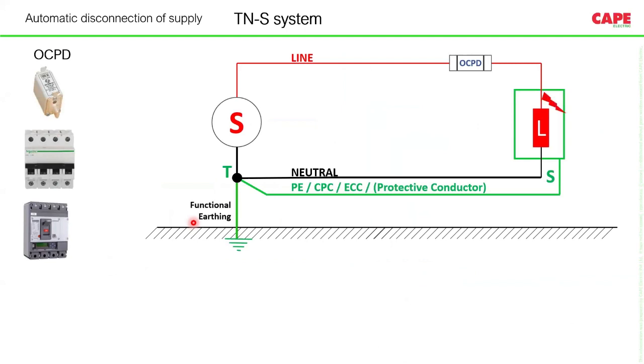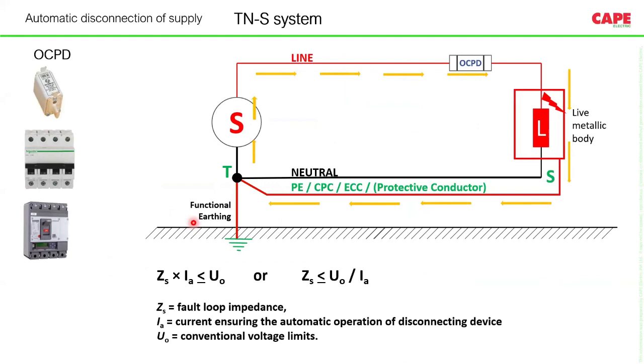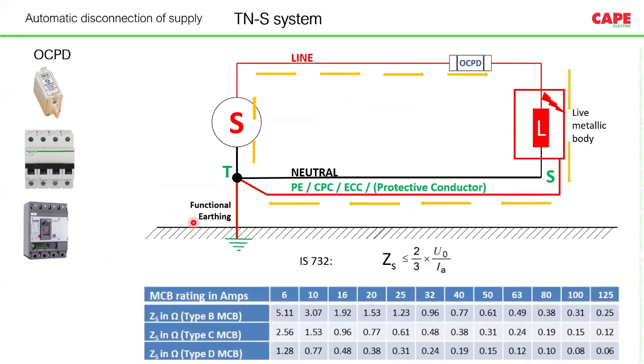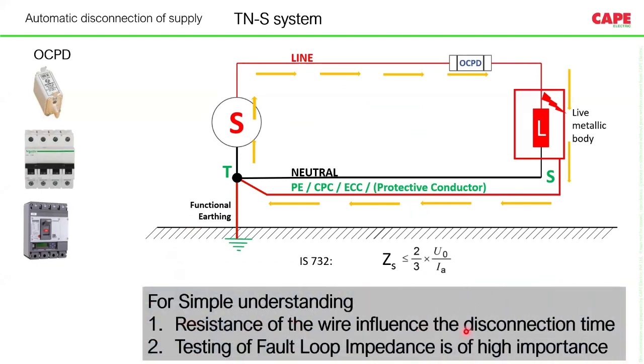Another important subject is fault loop impedance. Engineers who are practicing in hospitals, please note that equipotential bonding and fault loop impedance are both highly important. Both are included with very good explanations in the National Electrical Code. You can also find the tables, with fault loop impedance recommended for each type of MCB. So the simple method which you should understand is that the resistance of the wire influences the disconnection time. Testing of fault loop impedance is highly important.